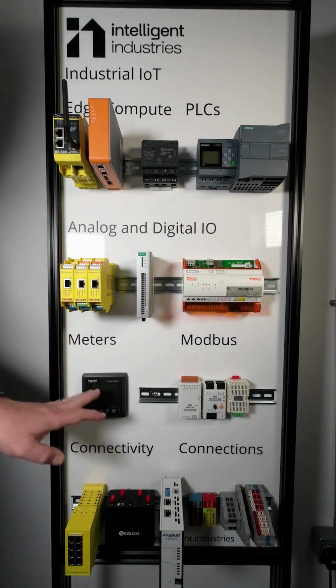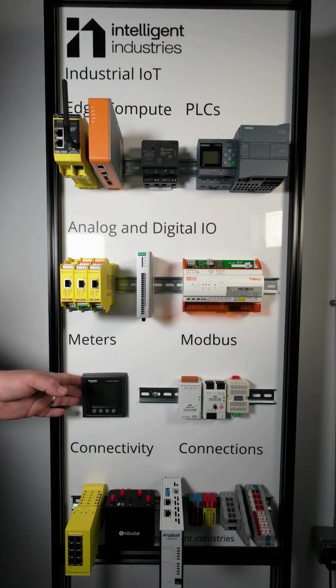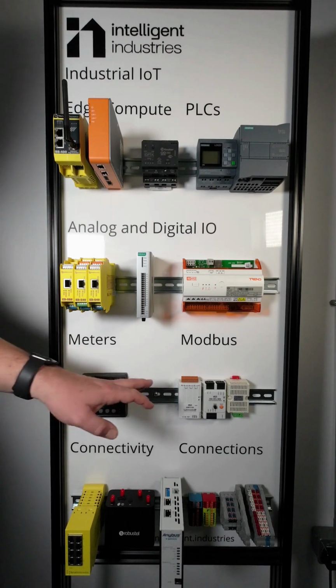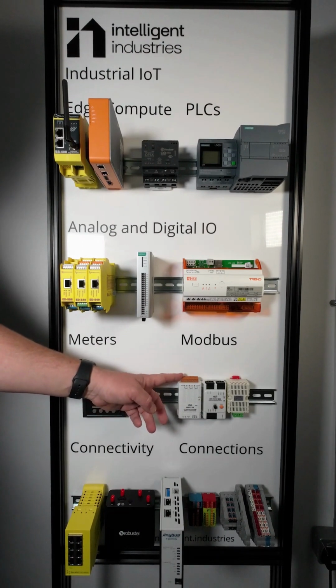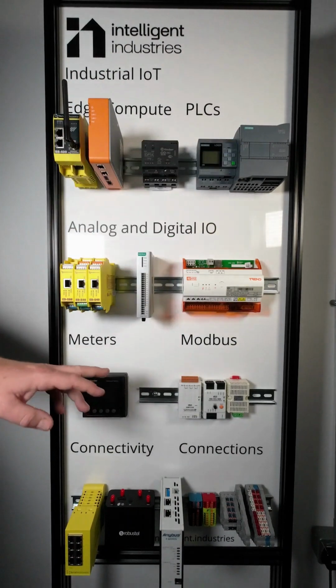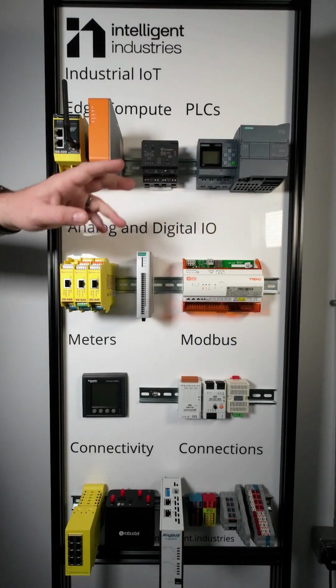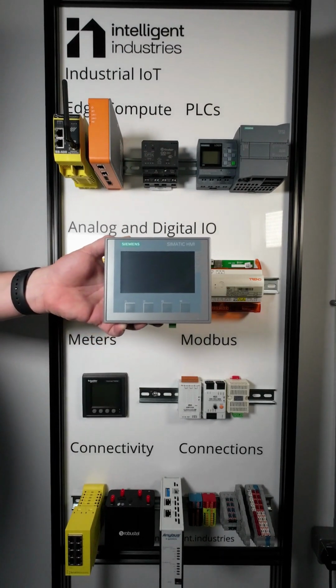Now these two sensors here and this one here, rather than using Ethernet, use what's called RS485 for communication. So it's an old Modbus technology that's been around for decades, and we can plug them into here and then convert from Modbus RS485 to Modbus TCP. This enables the newer devices that maybe don't support RS485 to talk to it.